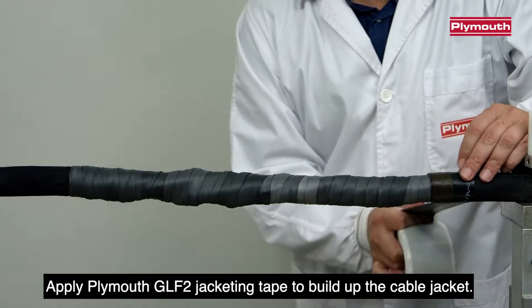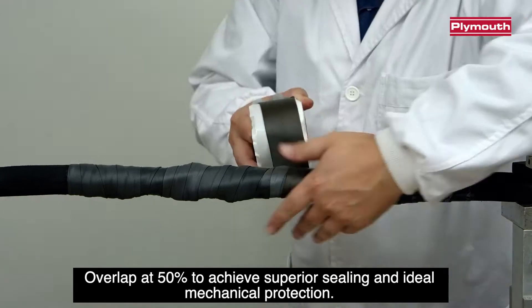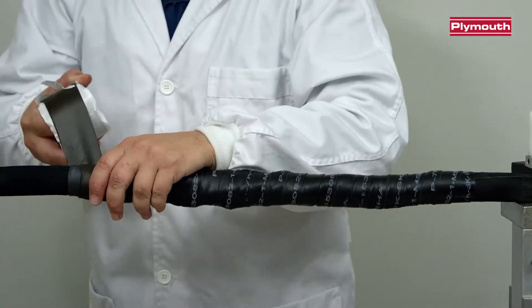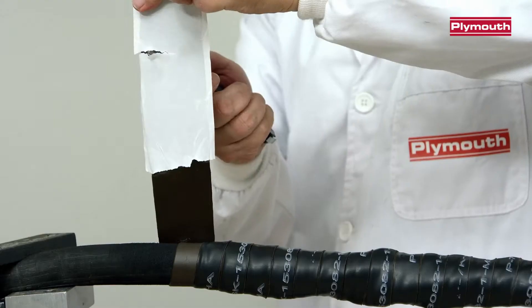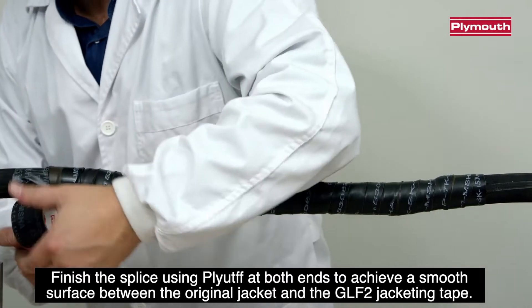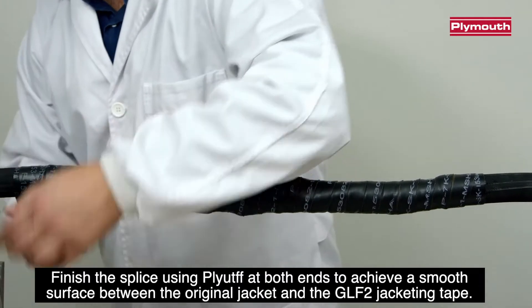Apply Plymouth GLF2 Jacketing Tape to build up the cable jacket, overlapping at 50% to achieve superior sealing and ideal mechanical protection. Finish the splice using Plytuff at both ends to achieve a smooth surface between the original jacket and the GLF2 Jacketing Tape.